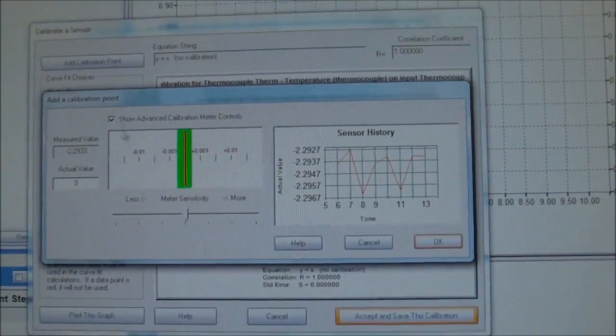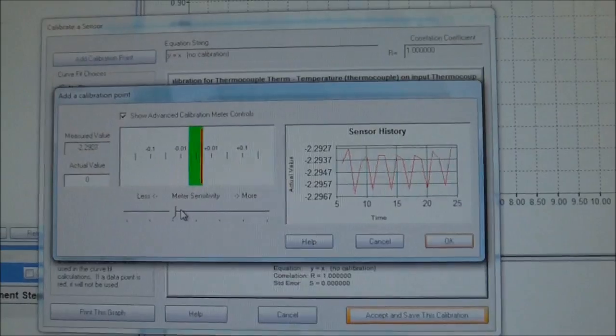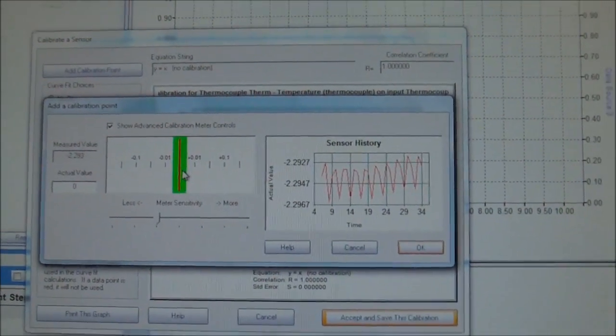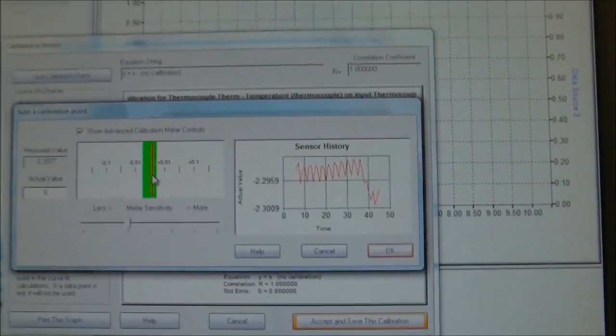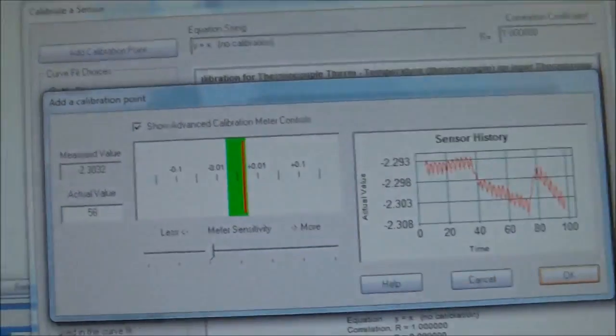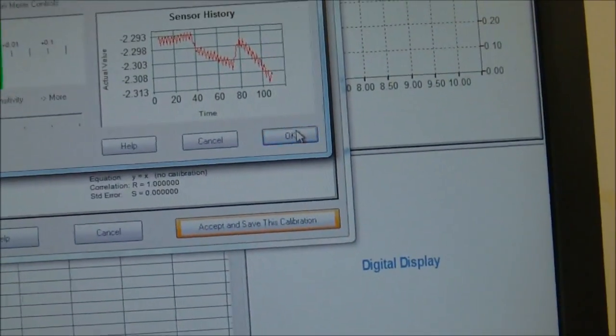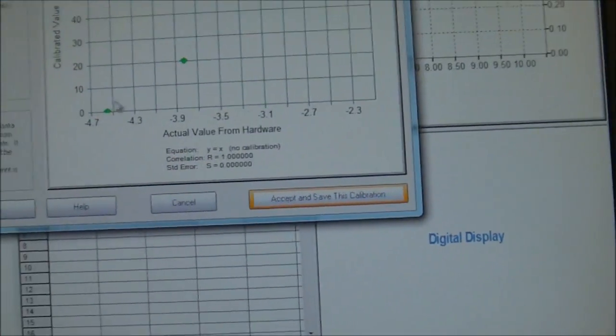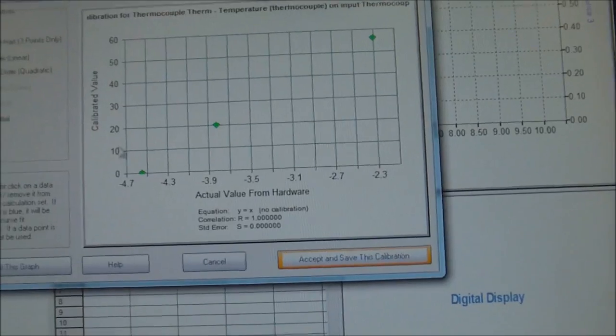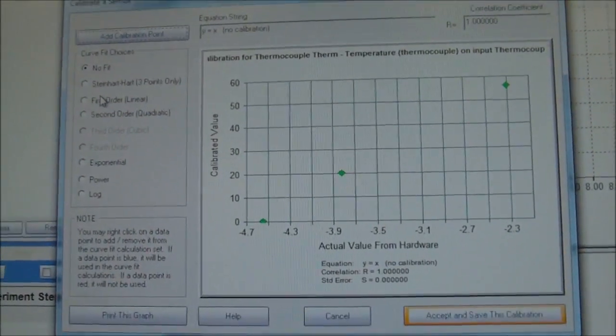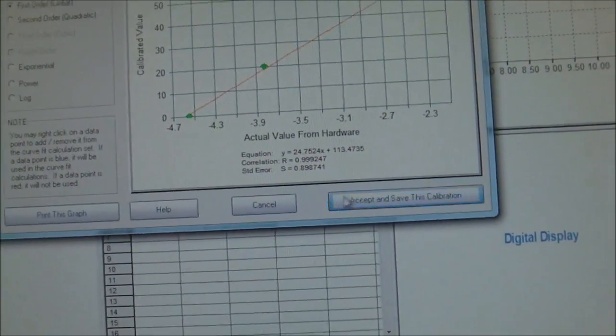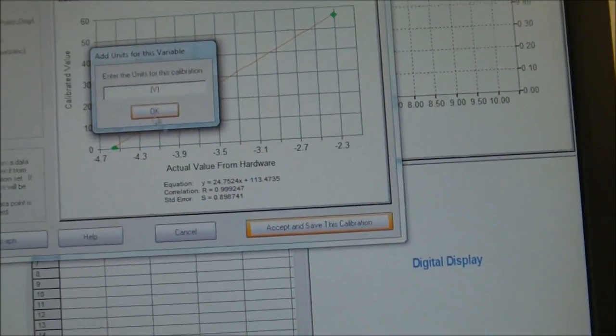I can click up here again and go down here, make sure that the thermometer is stabilized, that the thermocouple is stabilizing. Look at the temperature on there. And the temperature says 56 degrees. So we type in here 56 degrees, whatever the temperature says, and then I'm going to say OK. All right, now I can see that there's three points, and I'm going to fit them with a first order linear fit. And then I say accept and save this calibration.